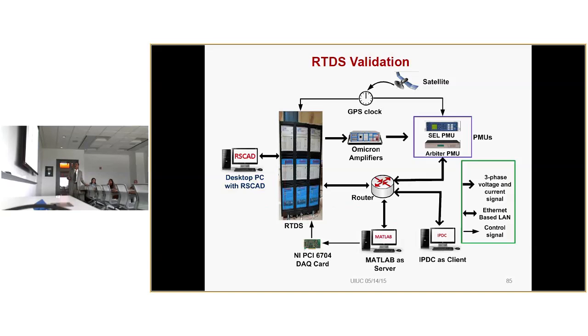So in the RTDS setup, our controller is sitting in this computer. Our phasor data concentrator, which is open source PDC software, was in another computer. And we have a limited number of PMUs, so at a few places we have connected to physical PMUs to get the data, that is line flow data. And we have soft PMUs inside RTDS. So they were brought to the phasor data concentrator. And one NI card we used to give the feedback signal to the generator excitation system. And we had written a program to create time delay, disorder, and packet drop.